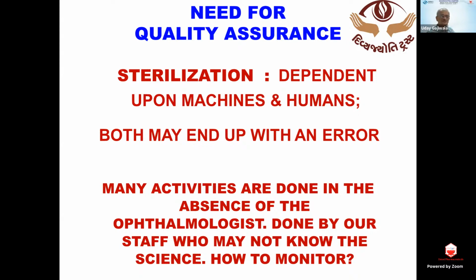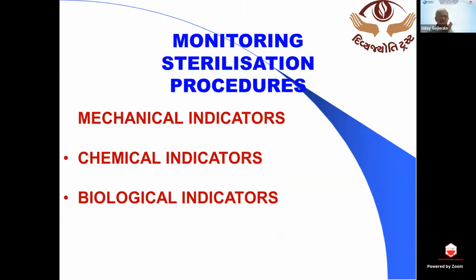Many times my junior colleagues, when I ask them to sign the autoclave strips register, they tell me, I did not observe the sterilization running of the autoclave machine. Why should I put my signature? Then I tell them, you are putting a signature saying that you have cross-checked the color of the indicator tape and it is jet black in color. That is what you are certifying. So we have to understand why each and every activity is being done.